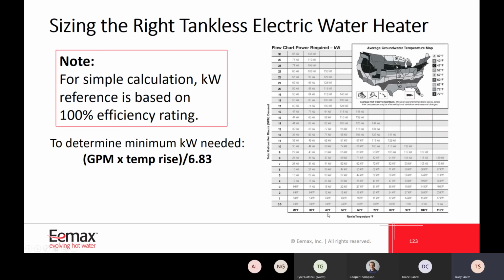If we know our temperature rise - the difference between our expected hot water temperature and our inlet temperature - shown here on the x-axis on the bottom, and we know our gallon per minute demand, we can see just how large a heater we need for a particular application.